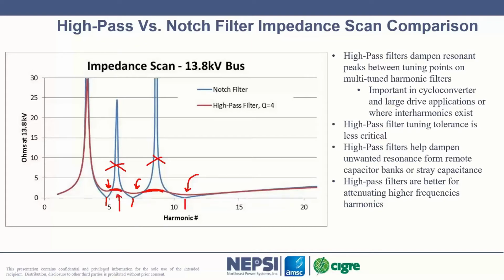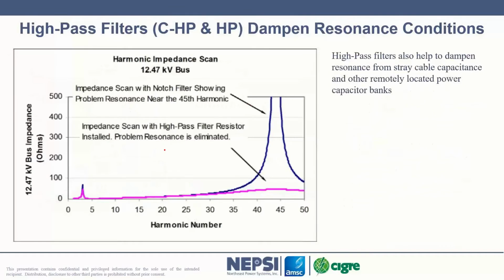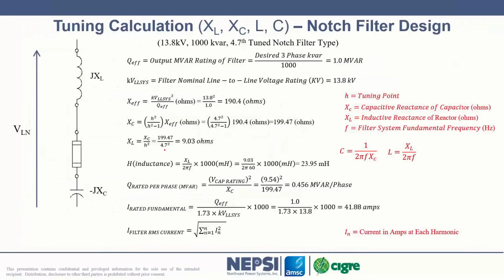If I have a harmonic current at this location, this would be true for a cycloconverter, potentially true for a steel mill, where I have what's called interharmonics or non-integer harmonics. Then I need to be concerned about this resonant peak. It would be a harmonic current injection times this value of ohms to give you sometimes a very high voltage distortion. So the purpose of the high pass versus the notch filters. Oftentimes you see high pass filters being used to dampen resonance associated with capacitance. And sometimes you see high pass filters applied in parallel with capacitor banks to dampen resonance. It's a technique that's often used.